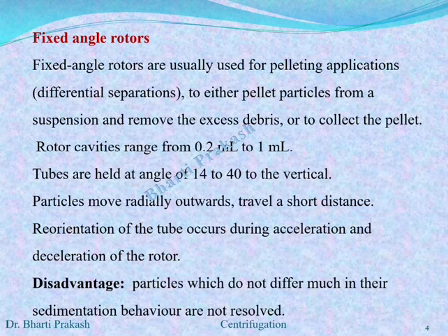The centrifugal force acts on the particle in the outward direction. So, when performing centrifugation in a fixed angle rotor, the particle does not travel in a straight line towards the bottom of the tube. It rather moves outwards within the tube till it hits the walls and then slides down this wall to be pelleted at the bottom.